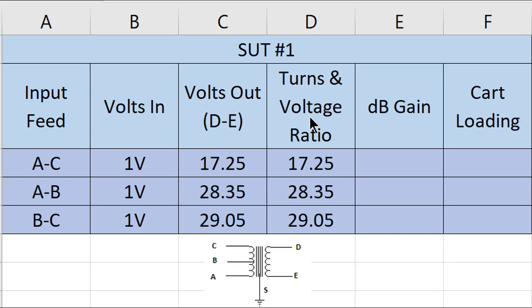Up next, we got to calculate ourselves the turns and voltage ratio. Well, the beauty of using 1 volt in and then measuring the output is you don't have a lot of math to do. You can figure it out just by saying, hey, we fed 1 volt in, we got 17 volts out. The turns ratio as well as the voltage ratio is 17.25. So for every 1 winding going from A to C, there are 17.25 windings on the output here. For every 1 winding going A to B, there are 28.35 windings on the output at E to D or D to E.